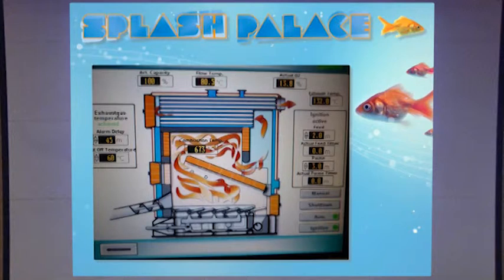And so the whole brains of the system are interacted on the front of the main control cabinet with a touchscreen. So this is quite an impressive bit of kit. The whole boiler can be controlled, set up, modified from the touchscreen on the outside of the MCC. It has a number of trend graphs that we can examine, and it also has a fault notification system that sends both emails and text messages to pre-programmed cell phone numbers via a small GSM modem that's also installed in the cabinet.